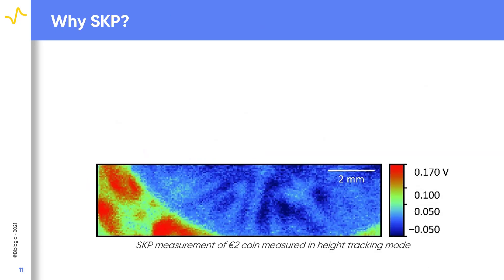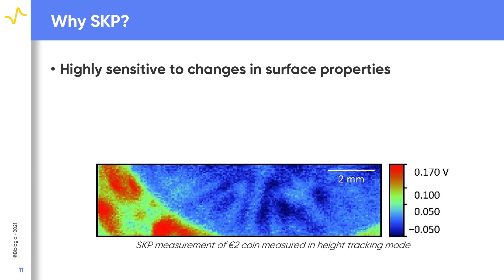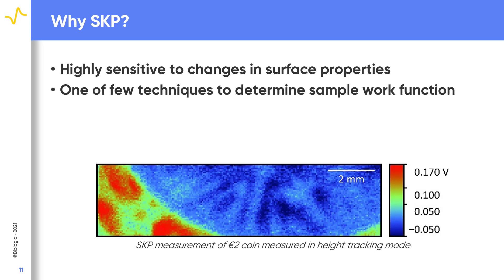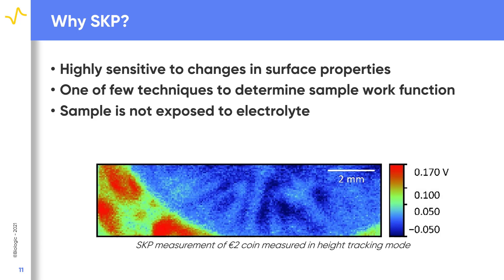What are the advantages of the SKP technique? SKP is highly sensitive to surface properties, making it useful for following changes in a sample surface, such as the formation of an oxide layer. By calibrating the SKP probe, it is possible to convert the contact potential difference to determine the sample work function, making SKP one of only a few techniques available to measure work function. Unlike other local electrochemistry techniques, in SKP the sample is not exposed to electrolyte, providing a snapshot of the sample at a given time. Finally, SKP performs all of these measurements in a non-destructive way.